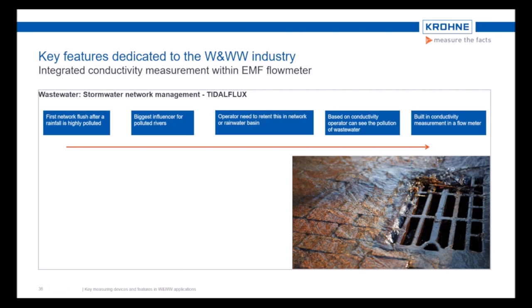Rainwater is thus a main cause of water and river pollution and must be handled with special care in future. Up to now, most rainwater tanks are operated manually and not automated. So in heavy rain events, a big amount of rainwater or mixed water can be discharged uncontrolled into the river. Legislation or regulations for measuring the amount and the quality of rainwater are currently under construction worldwide. Next to the flow measuring in partially filled pipelines, operators are therefore highly interested in measuring the quality by conductivity of the stormwater wastewater.